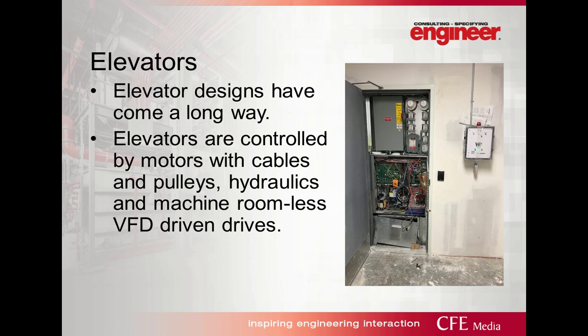Thanks, Rich. Elevators, real briefly, have come a long way in our times. And it's important to pay attention to the elevators that are going into your building because some of them are used for firemen's egress purposes and for service of the building. The most important thing that I've come across in the recent past is, again, that a lot of times the elevator inspectors don't understand the difference between emergency power and legally required standby power. Legally required standby power is the typical power source you're going to use for your elevators in your building. However, it doesn't limit you to say you can't use emergency power.